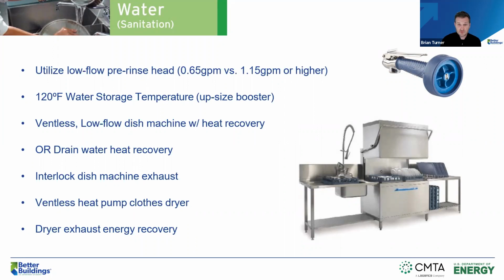There are a lot of ventless dishwashers now that incorporate integral drain heat recovery. We have been burned by that—they're fantastic, they save a lot of energy, but you really have to pay attention to how you're designing the room and the exhaust rates, because they can let out an enormous amount of steam at the end of the cycle when you open them. If the exhaust rates haven't accounted for that, you could have an angry owner. So there's a trade-off: you don't want to too heavily exhaust the dish machine room, and you need to weigh air change rates against the energy you're saving with that ventless dishwasher.